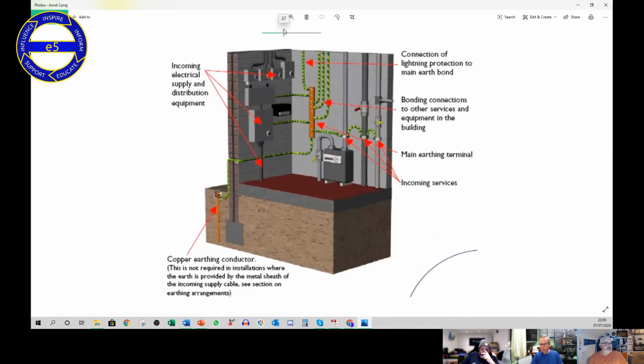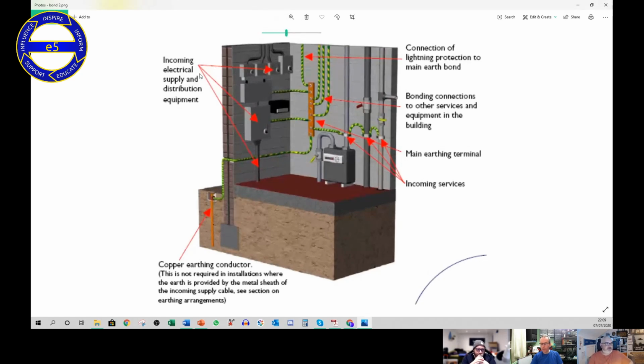And the last one, which is my personal favorite, because it kind of just shows everything in context. The incoming supply and equipment, you can see there, it could be a switch fuse into some sub metering and sub switch fuses, but you may have a copper earthing conductor, i.e. a TT, goes to a main earthing terminal, and any other extraneous incoming services are bonded, looped across at the point of entry to the building, and then other earthing systems like lightning protection. And all that means is if there are any electrical hazards or any faults on the fixed electrical installation, that earth bar will be energized, charged with voltage, and all of the pipework will rise in voltage within milliseconds, hopefully. Otherwise you'll feel it and you'll get quite badly hurt.